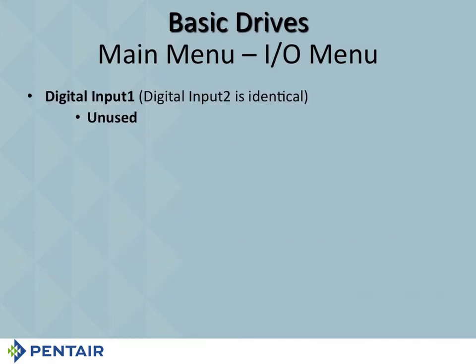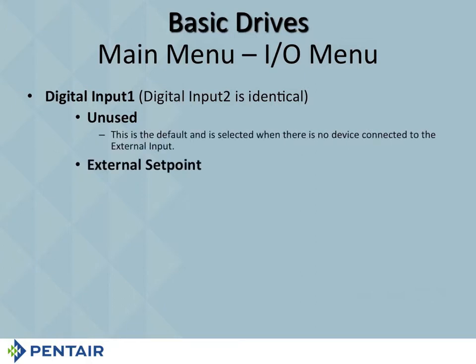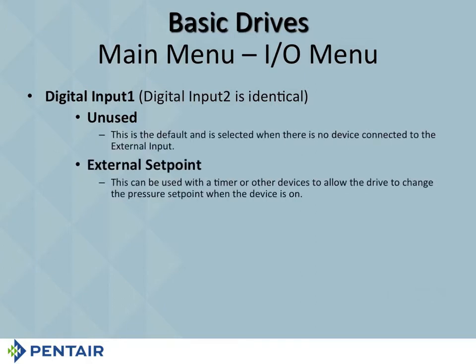Now, digital inputs, we send them out unused. Remember, there's 2 of them. They're identical. You can set them for external set point. What this means is I want to run a different pressure. Say, for example, I'm running a sprinkler system, and I want my sprinkler system to run at 70 psi, but I want my regular system, my house system, to run at 60. Remember that when you change the pressure, you are changing the pressure in the whole system. So if you change it up to 70 or down to 45 for your sprinkling system, your whole house is going to be that way until the sprinkling system turns off.